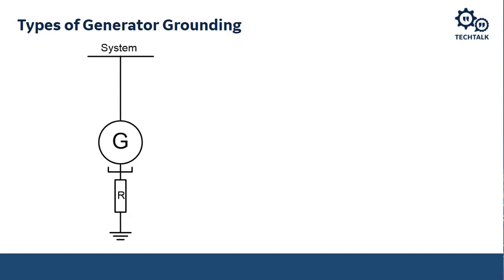it can get very expensive depending on the rating of that resistor. For low impedance, as with a solidly grounded system, if there is a ground fault, especially an internal ground fault in our zone, it can cause internal permanent damage to the equipment. And we're talking about, especially for a generator, it doesn't need a lot of ground current to cause internal and permanent damage to the equipment. So when we're looking at low impedance to ground, this can be a couple of hundred amps to a couple of thousand amps, depending on the type of resistor that you use.